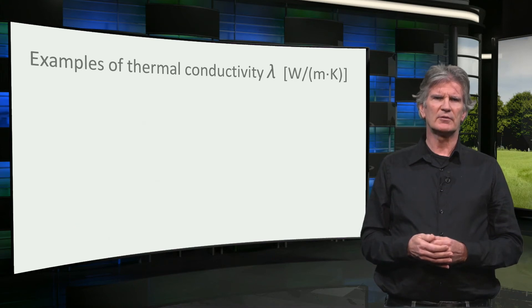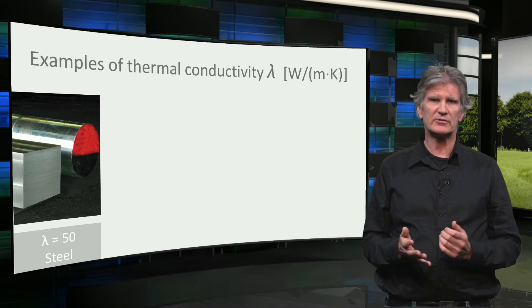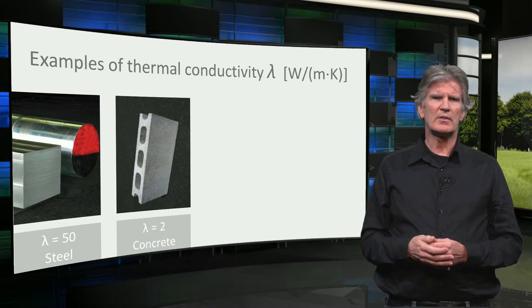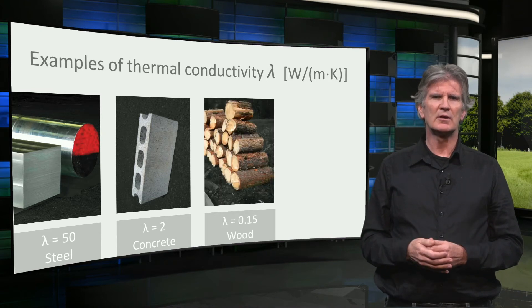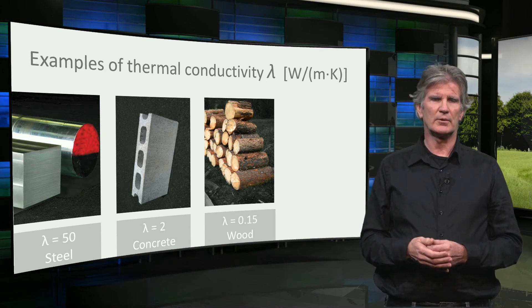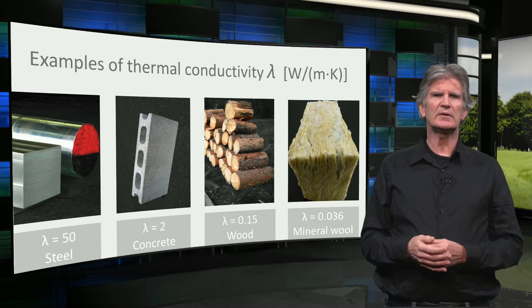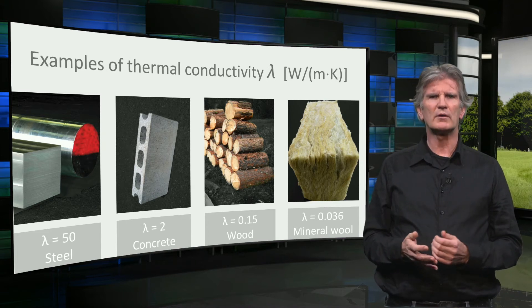There are generally speaking four groups of materials. Metals with a very high thermal conductivity higher than 50, like steel. Stony materials with a high thermal conductivity around 1.5 — concrete, for example, has a thermal conductivity of 2. Wood and plastics with a relatively low thermal conductivity — wood, for example, has a thermal conductivity of 0.15. And insulating materials like mineral wool, with a very low thermal conductivity less than 0.05. In the course reader and on the internet you can find the thermal conductivity for all kinds of building materials.